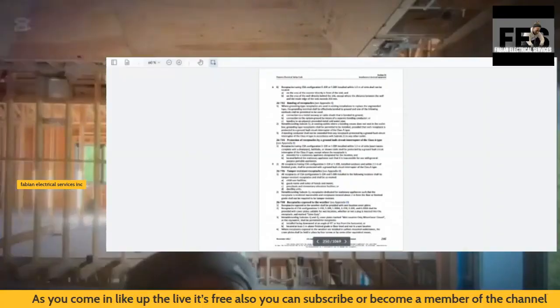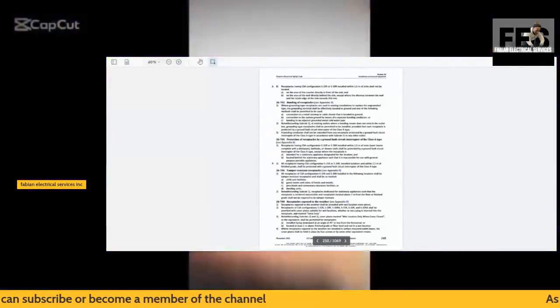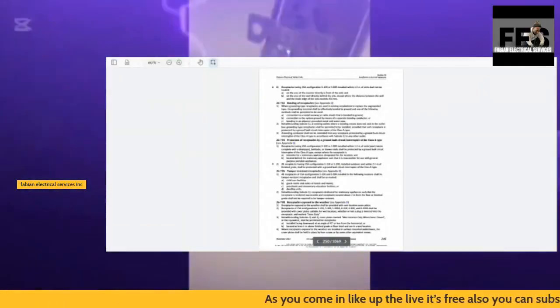Notwithstanding, for existing outlets where a bonding means does not exist in the outlet box, grounding type receptacles shall be permitted to be installed, provided that each receptacle is protected by a ground fault circuit interrupter of the Class A type.